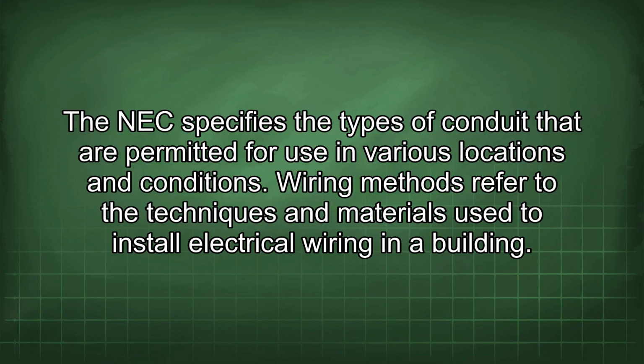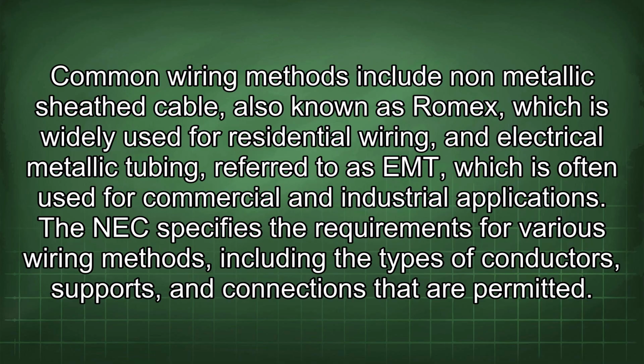Wiring methods refer to the techniques and materials used to install electrical wiring in a building. Common wiring methods include non-metallic sheathed cable, also known as Romex, which is widely used for residential wiring, and electrical metallic tubing, referred to as EMT, which is often used for commercial and industrial applications. The NEC specifies the requirements for various wiring methods, including the types of conductors, supports, and connections that are permitted.